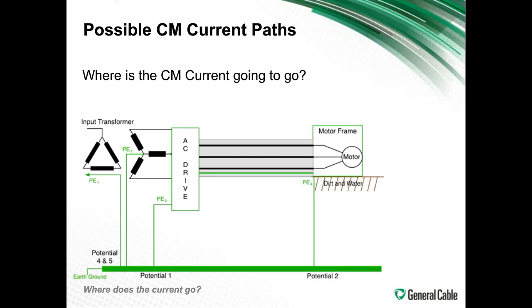So what happens is you want the cable to take the current and bring it back through the ground, and so it takes care of that excessive current that's in the system. Well, what happens is a lot of times when you don't have a proper system, the current finds a way to leak any which way it wants to in the system, and this is what happens. So this would be a common mode current that goes through from the drive to the motor. Where is it going?